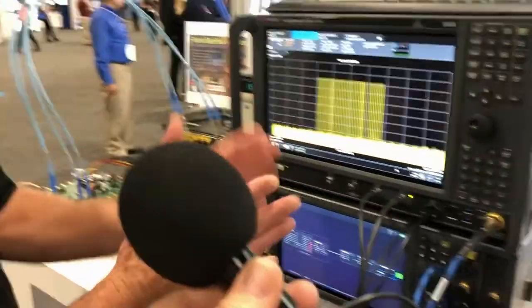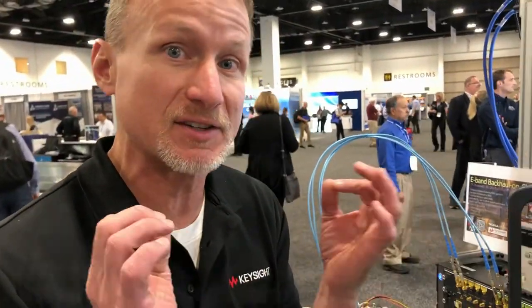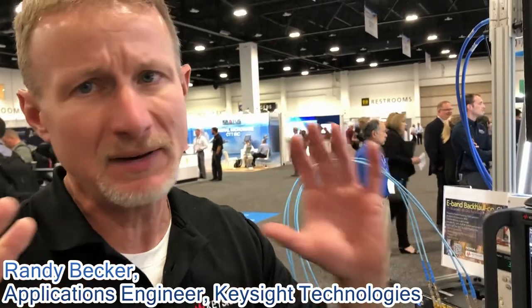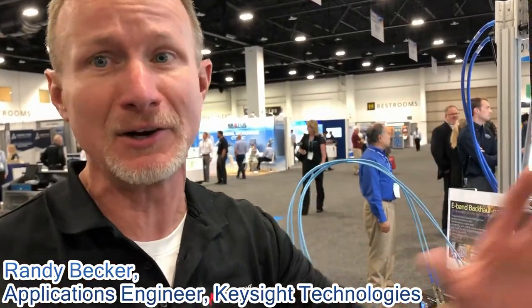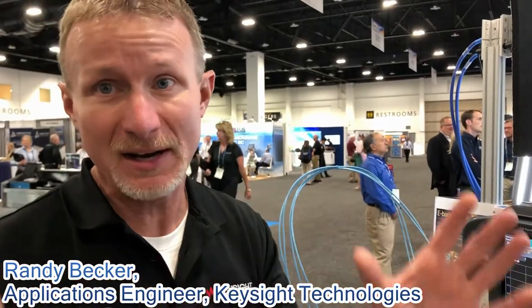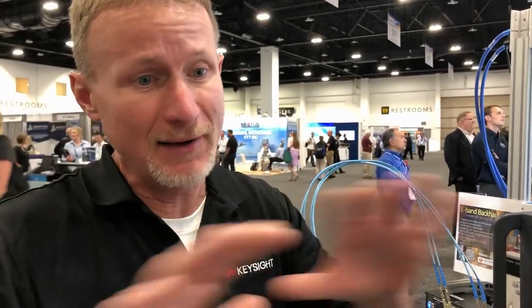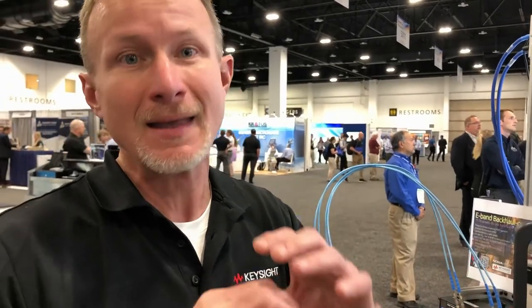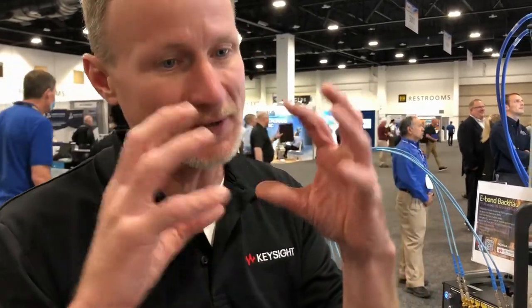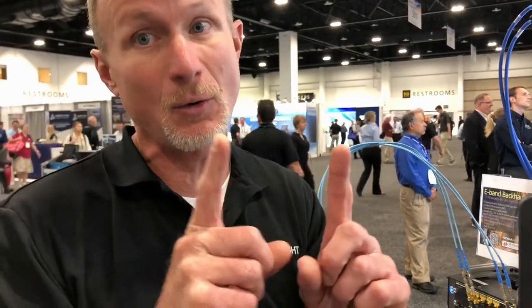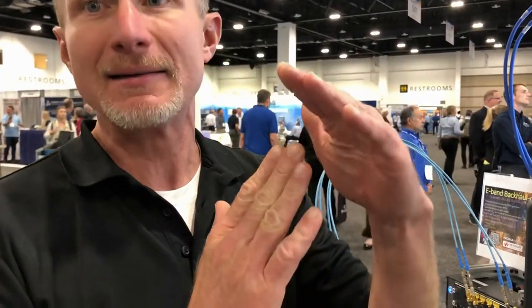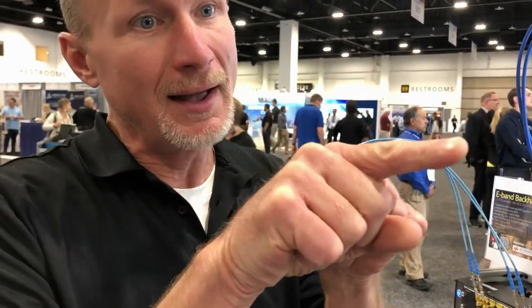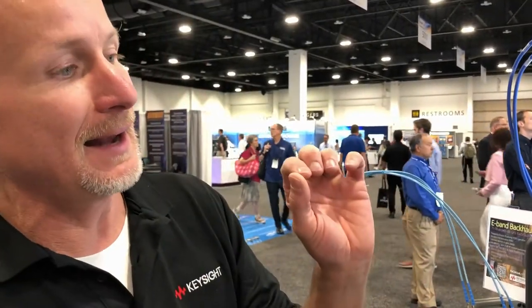So this is Keysight's latest, greatest microwave vector signal generator. It's based on a direct digital synthesis architecture, which eliminates all of the many issues we've been combating for many, many years with generators that are all based on IQ modulators. Until today, that's how every generator has been put together. And you can never get those IQ modulators perfectly balanced, especially as you go wider and wider in bandwidth. You can't keep them 90 degrees quadrature all the time. You have little phase offsets, DC offsets, and I'm going to show you what a representative signal looks like when played on such a signal generator.